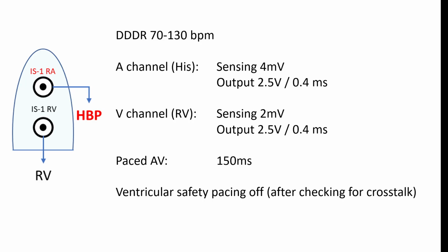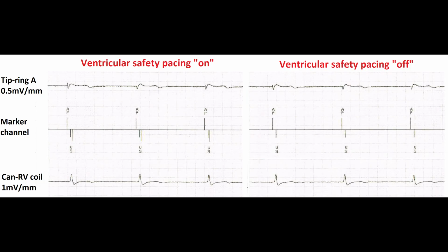The device is programmed as shown, and because ventricular sensing is ensured by the ventricular lead, there's no need for the His lead to sense, and that's why the sensitivity is programmed to the maximum value of 4 millivolts. In order to avoid unnecessary ventricular pacing, the ventricular safety pacing is inactivated after having checked for crosstalk. And these are the marker channels with the ventricular safety pacing activated and inactivated with pacing by the His lead and sensing by the backup ventricular lead.